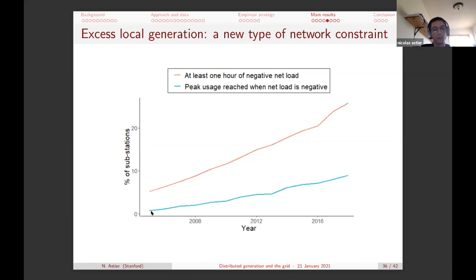It was less than 1% of substations in 2005, and those were small mountain area substations where you had some hydro and very little load. But we can see that this has been increasing steadily, and as of 2018, you get about 8% of substations where you actually reach their peak usage during a backfeeding hour. And this trend is very unlikely to stop, because if you look at the number of substations for which a negative net load happened at least 1 hour during the year, so there has been at least 1 hour where local generation was higher than local consumption, it has also increased steadily, and now about a quarter of substations are like this. So this feature that you depress the lowest quantile significantly, which used not to matter that much, is going to start mattering more and more, because you would have to either invest in the grid or curtail or store, but you would have to do something about it.